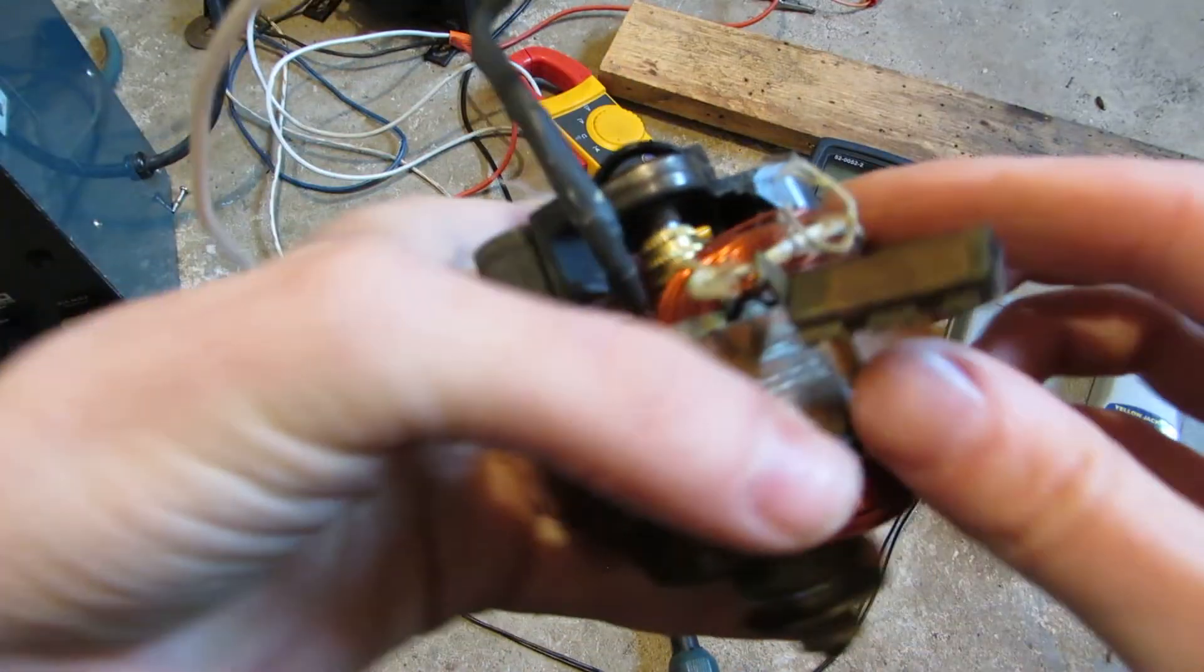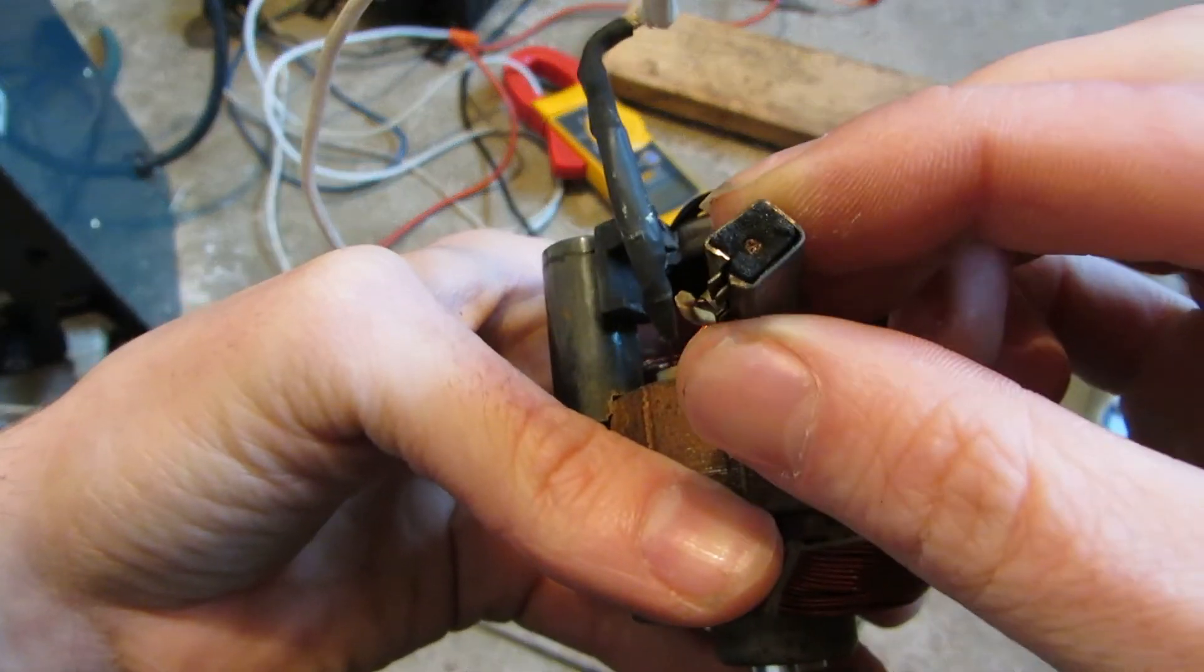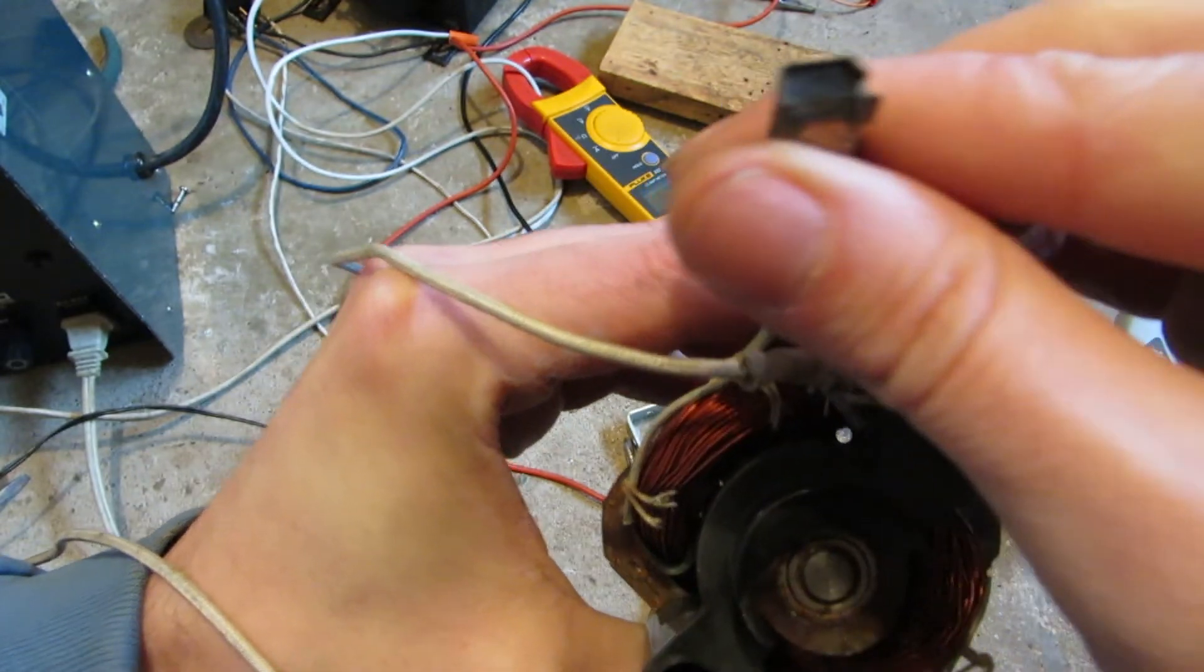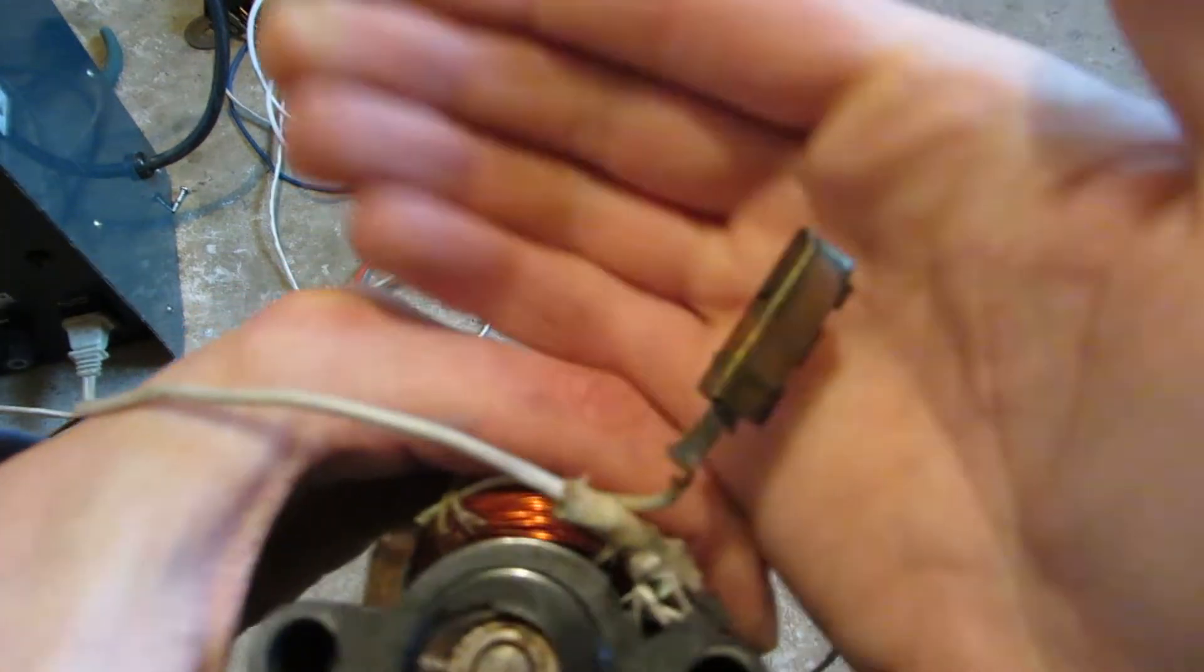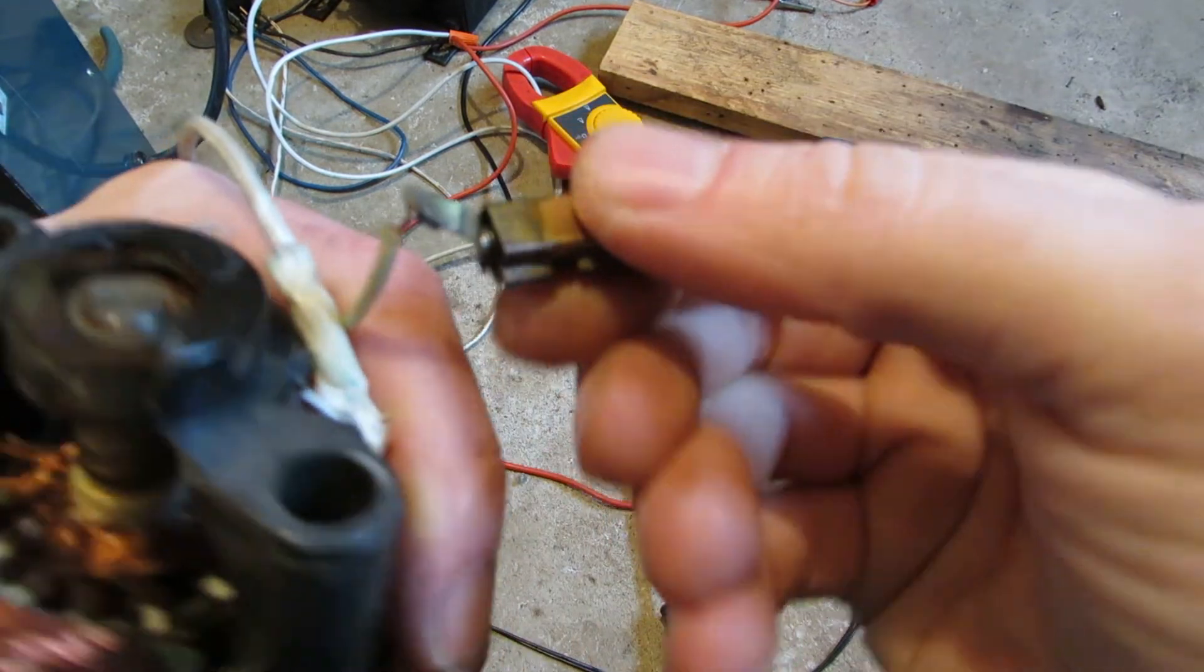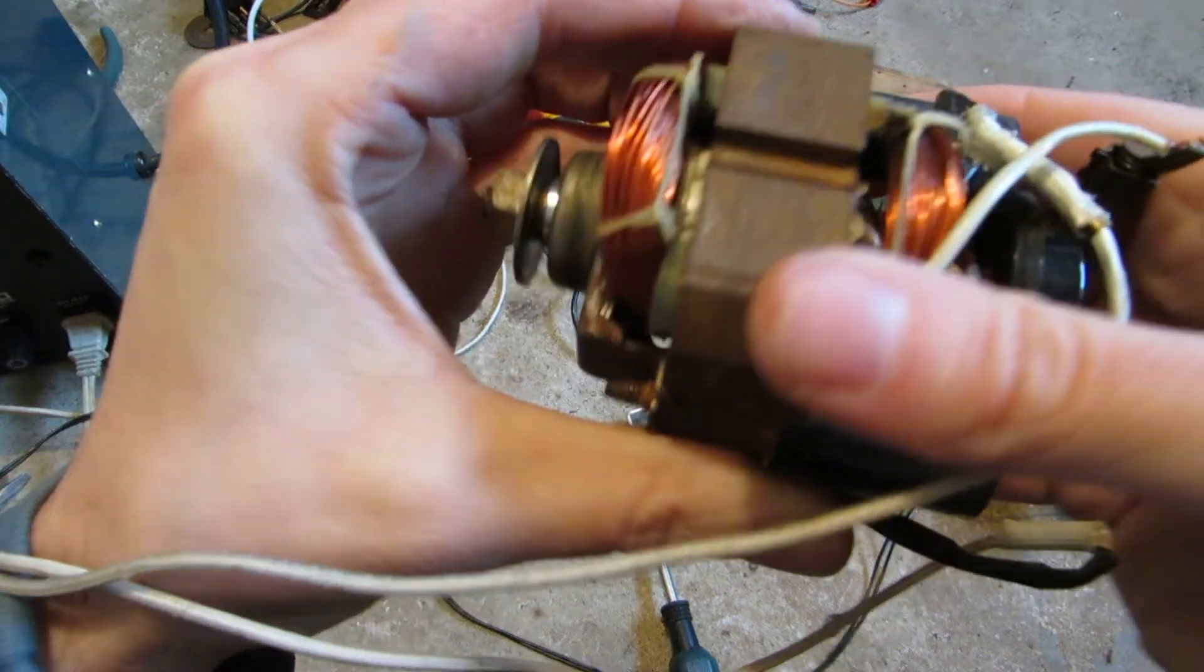So there's one of your brush holders. The brush looks like there's a little bit of brush still in there. Oh, the other one's got a nice dent in the front of it. I don't know how much brush is still in there. But yeah, so that was motor number three.